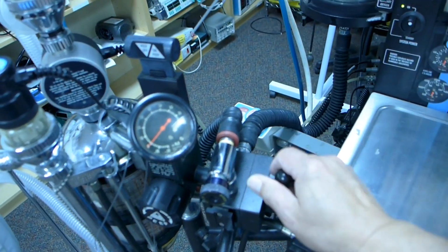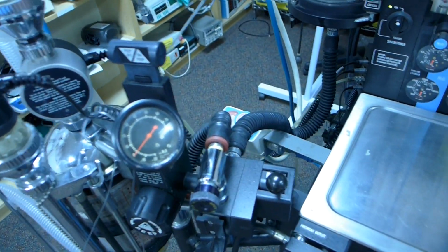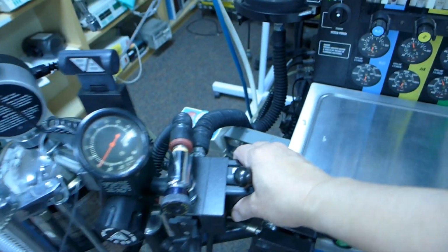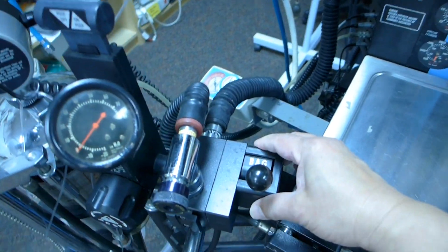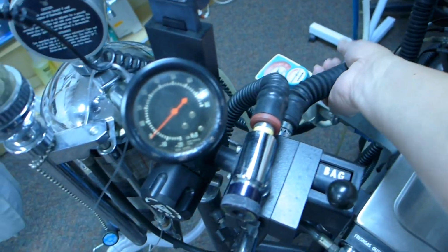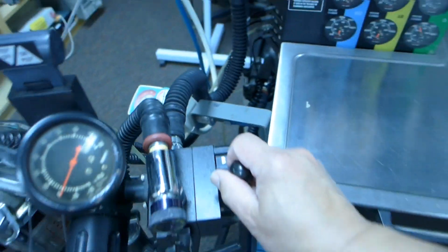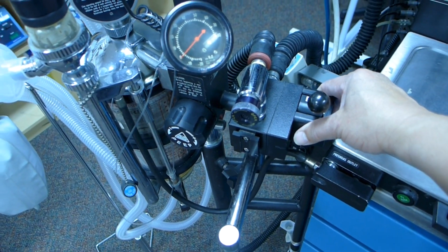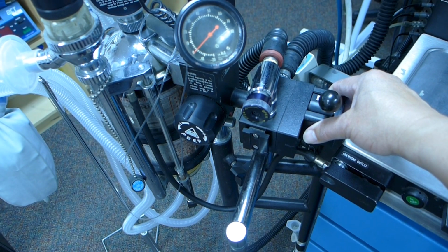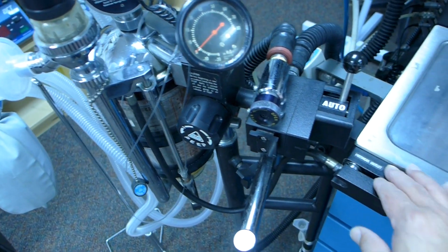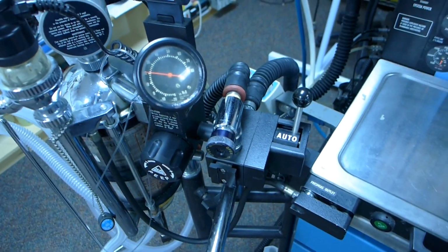Okay, so this is the selector switch. Normally, the doctor uses this on the bag mode when they start to induce the patient with anesthesia gas from the beginning of the case.